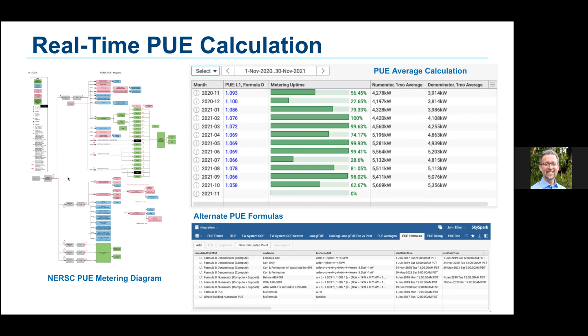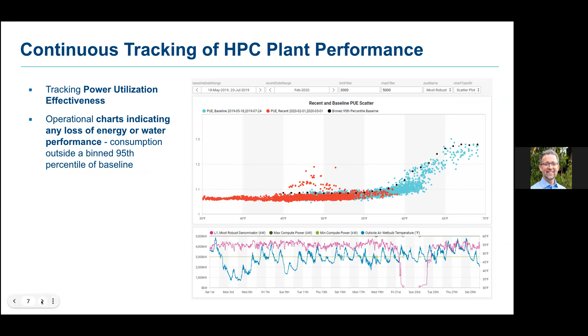But of course, it's more interesting instead of an average PUE to look at it in other ways. Often how we're looking at these data are in scatter plots, where outside air wet bulb temperature is on the x-axis and our metric of concern is on the y-axis. So you can have a baseline of operation that we're comparing against, that's in the teal color, and then a performance period in red. We'll often calculate a 95th bin percentile as the way just to establish a threshold. So if we see performance that's outside of what we've generally seen in the past, we'll go and investigate that. And we have this for many different metrics.